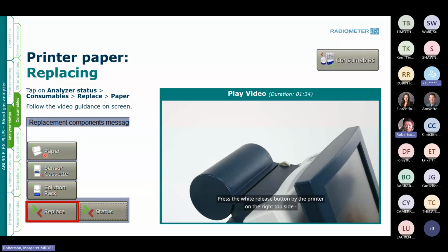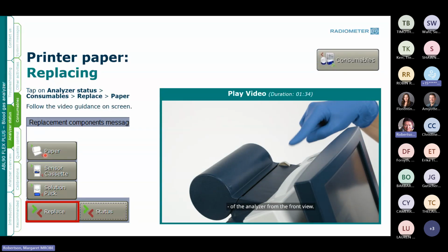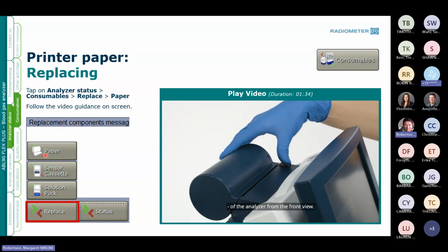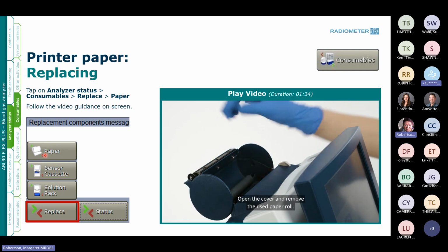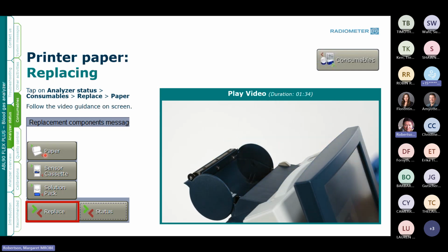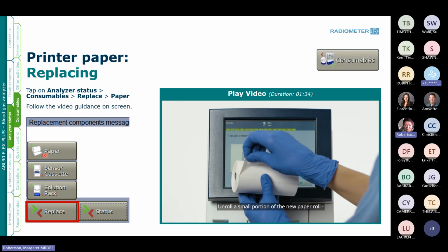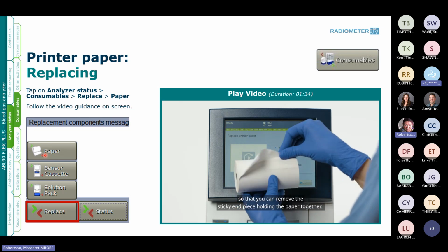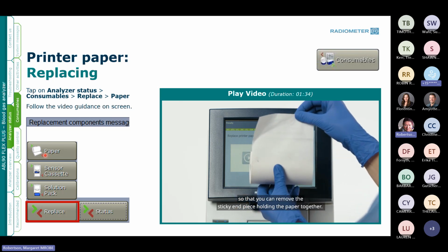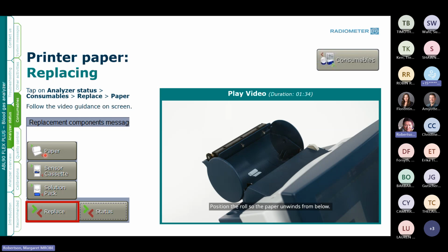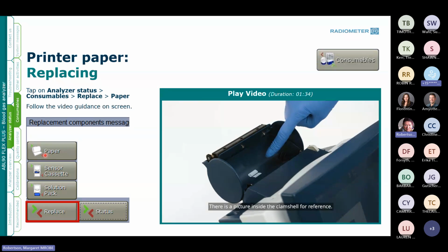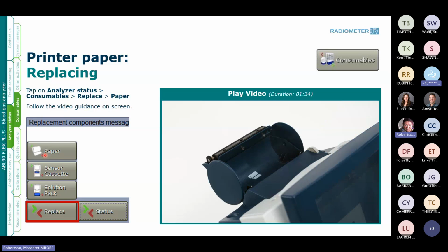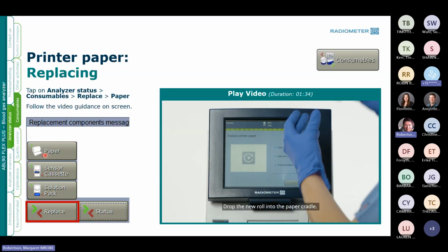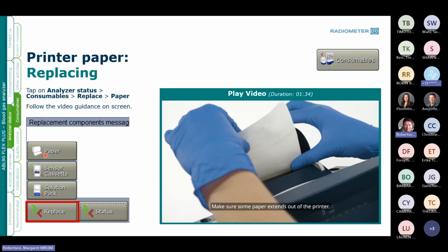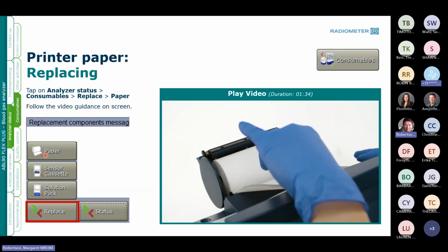Press the white Release button by the printer on the right top side of the analyzer from the front view. Open the cover and remove the used paper roll. Unroll a small portion of the new paper roll so that you can remove the sticky end piece holding the paper together. Position the roll so the paper unwinds from below. There is a picture inside the clamshell for reference. Drop the new roll into the paper cradle.